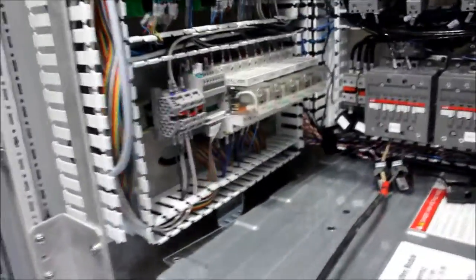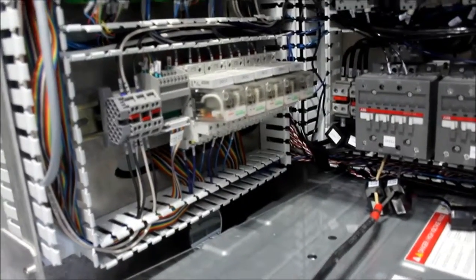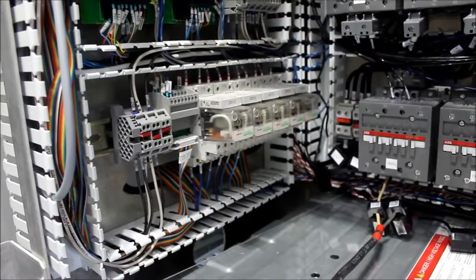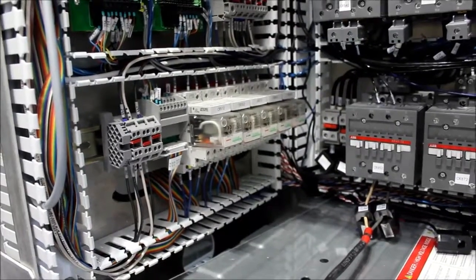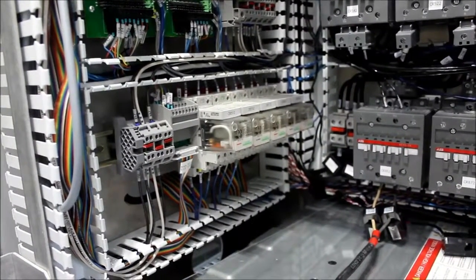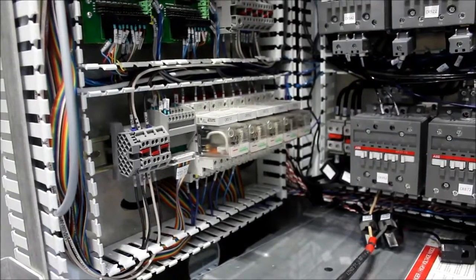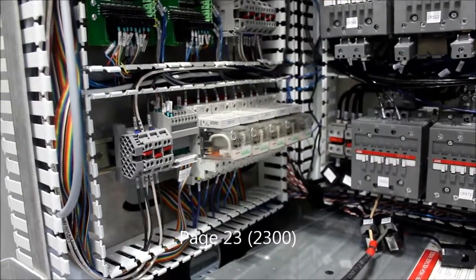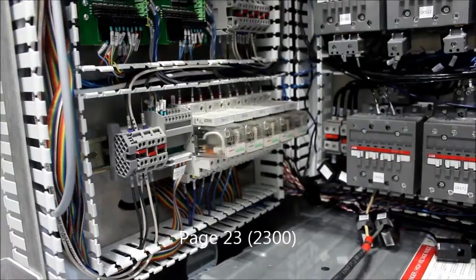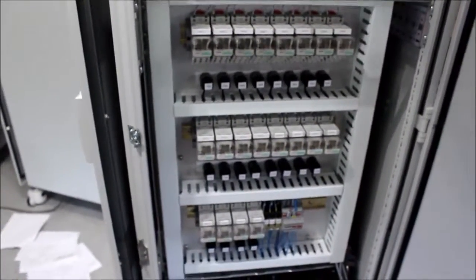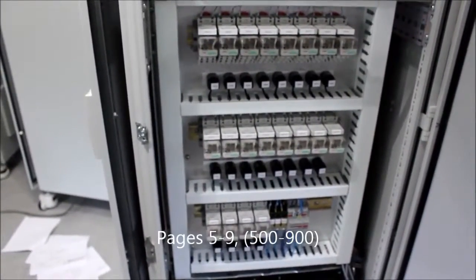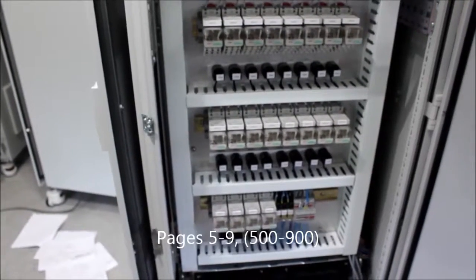Some internal load control contactors used for proper battery operation, including soft start, so that a sudden current connection to the control electronics doesn't damage the batteries, are shown here. And then on the right side of the unit, the remaining load control relays are available. These will be used to control all of the 120 volt loads inside of a residential structure.